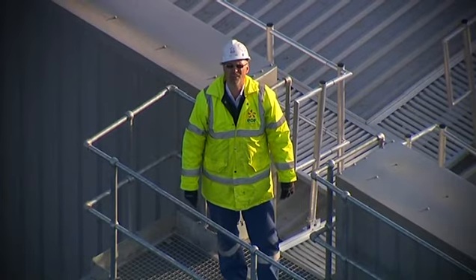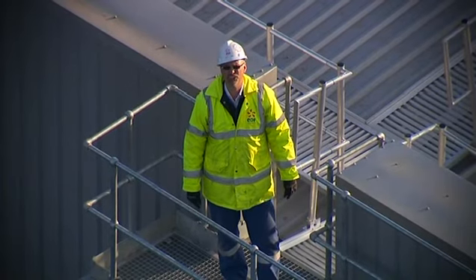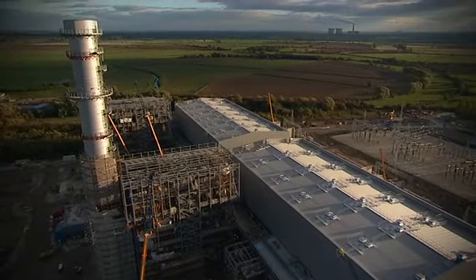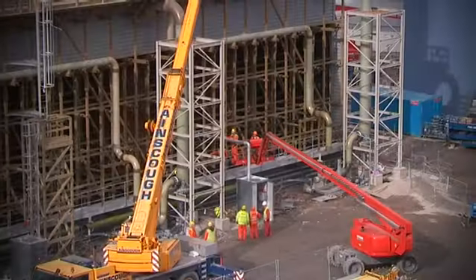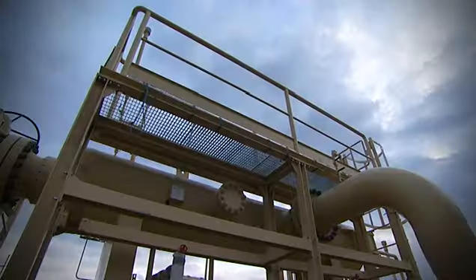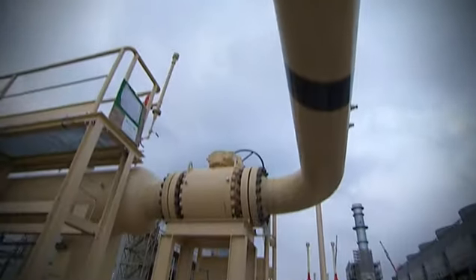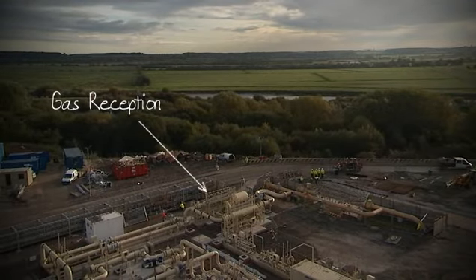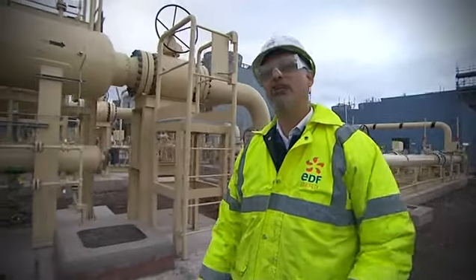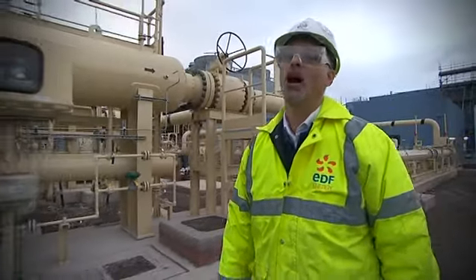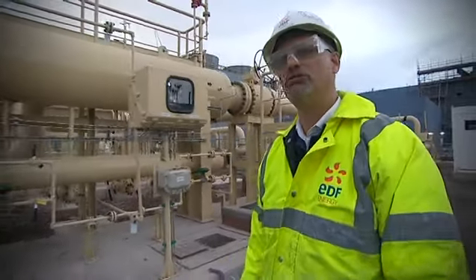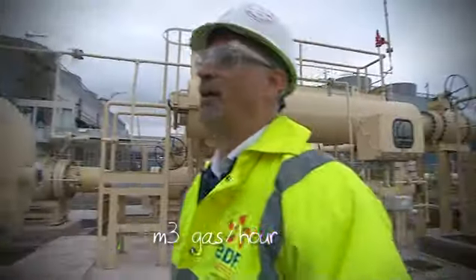My name's Andy Lowe. For those of you who haven't worked on a CCGT station before, this is it, and I'm going to show you how it works. It all starts with gas. We've built a 19-kilometre pipeline from a place called Grayingham, north of Gainsborough, and it arrives on site through a 24-inch diameter pipe under the River Trent to the gas reception facility. Here, the gas is metered, filtered, pressure reduced, and then reheated for consumption in the gas turbines. On average, each gas turbine will consume 250,000 metres cubed of gas per hour.